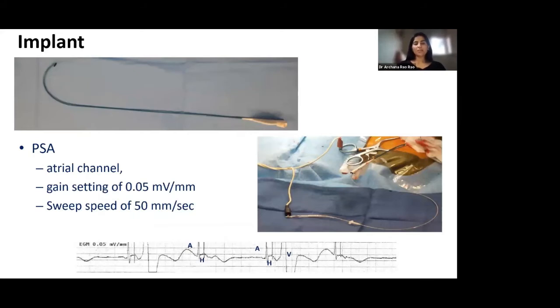The PSA itself, a few words of caution: if you do have an EP system, it's much better to be using the EP system, as it's much more visually easy to identify the His lead and the His bundle. If you do not, then a patient analyzer is sufficient. You need to program the atrial channel. You need to turn the gain settings to the lowest gain so as to be most sensitive to identify the His spikes. And you need to have a sweep speed of at least 50 millimeters per second, ideally 100 millimeters per second, so as to visualize the atrial, the ventricular, and the His complexes properly as you're even trying to identify it.